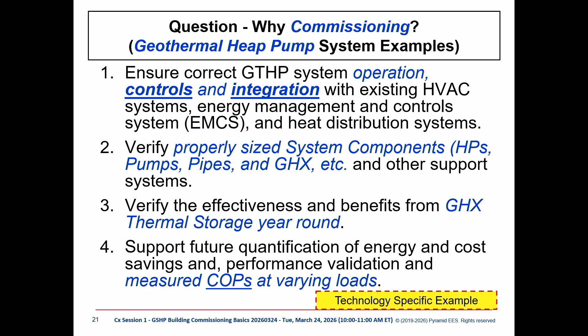COPs at various loads—yesterday we were on the tour, and some sites might know the COP, some don't know what the COP, the coefficient of performance, is. By having a proper building management system and data points, you can automatically calculate this. Sometimes with chilled water plants we call it wire to water—how much electricity comes from the wire, how many BTUs we send out. You can call it whatever you want, but without having the proper tools, you're not going to be able to see this number.